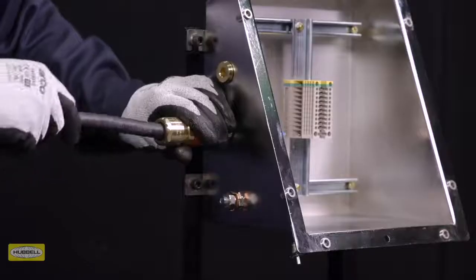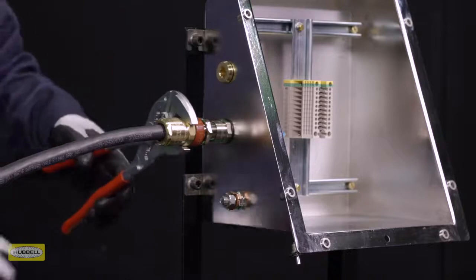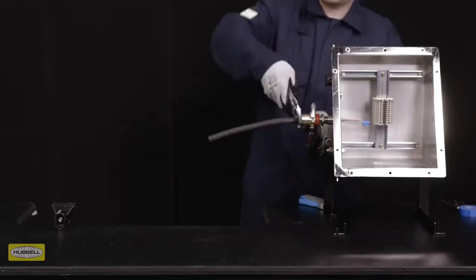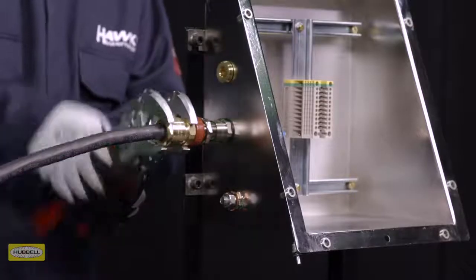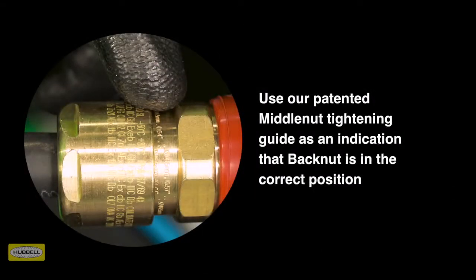Hand-tighten the back nuts until the seal is formed around the cable. Use a wrench or spanner to grip the middle nuts while preventing the middle nut from turning. Use a second wrench to apply one further full turn to the back nuts. Use our patented middle nut tightening guide as an indication that the back nut is in the correct position to suit cable diameter.